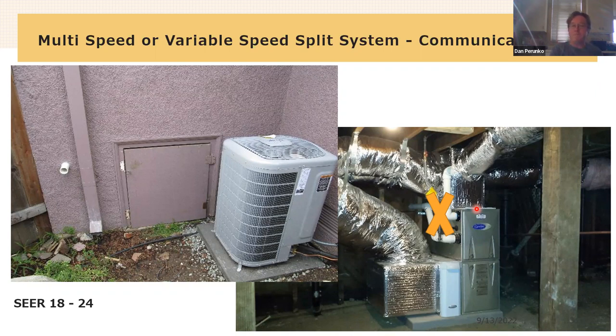The only argument for this sort of gas electric hybrid would be in a scenario where the customer couldn't have solar, their dollar cost for operation got really high for electricity, and they would want to shift to gas heat. But 99% of the time that argument doesn't hold up. So I've completely stopped installing this system. I do have one or two jobs a year where there's no generation of any kind, and we end up doing a gas heat and air conditioner scenario. But it's only sort of when we're forced, right? Like when there's just no way they can have any kind of generation.